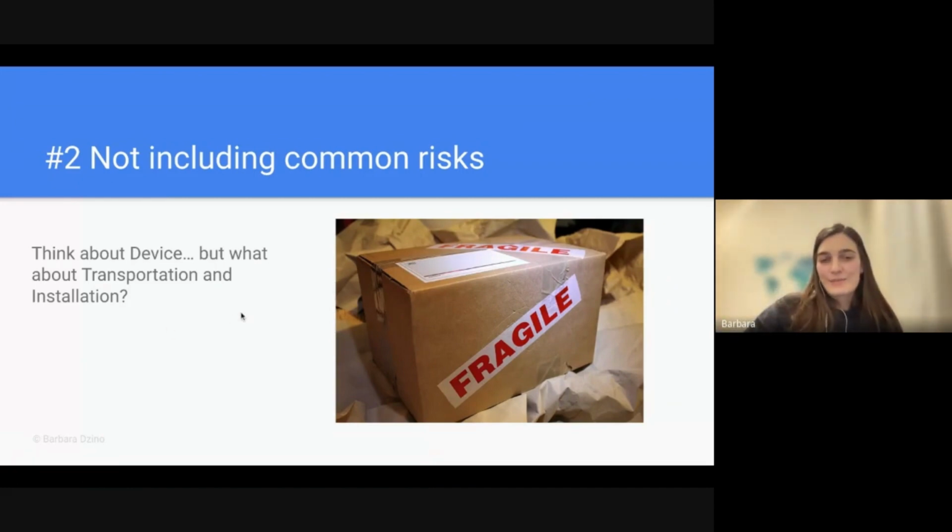And yeah, installation, people know how to install an app. It was quite fun to us when apparently we had to document how we transport the device as well. It's a standard that you ship the box you have of the device, even if it's super padded, etc., in plastic and all. You have to ship it around for a bit and then check again if everything works as intended.